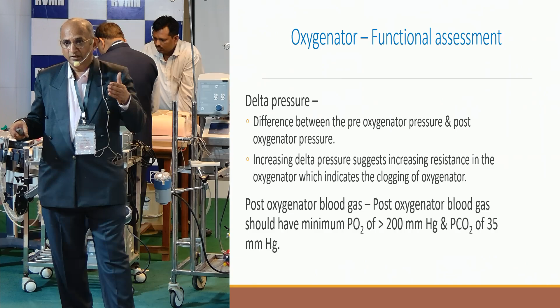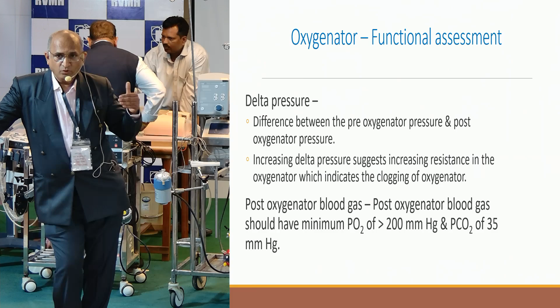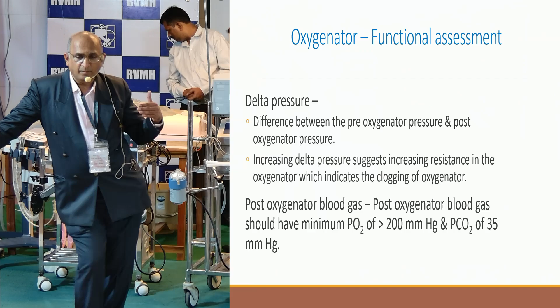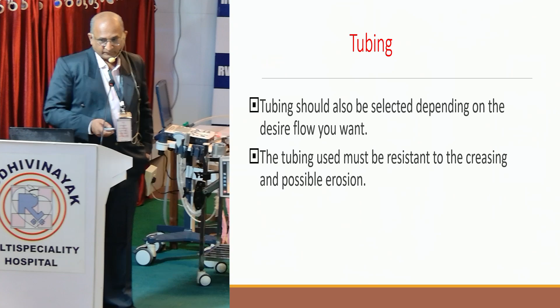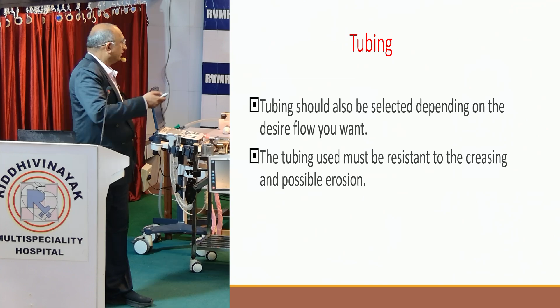So if, when you initiate ECMO, the delta pressure was, say, 25, and after 10-15 days you find that the delta pressure has increased from 25 to 50, it means the oxygenator is getting clogged. So when the value goes above 2 times the baseline delta pressure, it means the oxygenator is getting clogged. That trend is important, not the single value. Then you have different size tubings: 3/8, 1/2, 1/4 tubings.